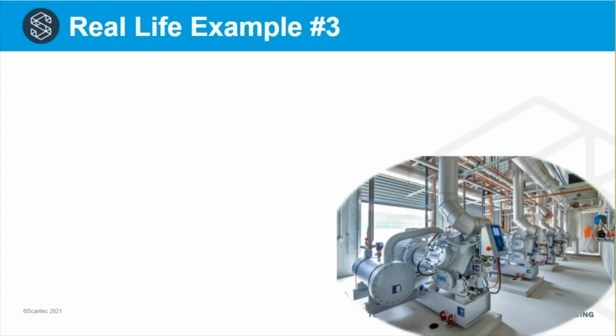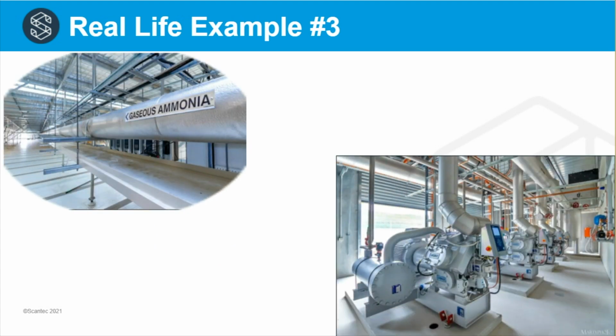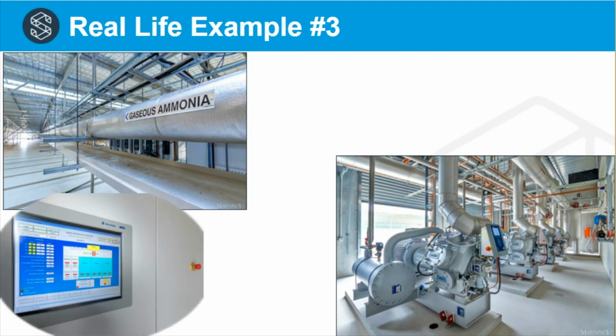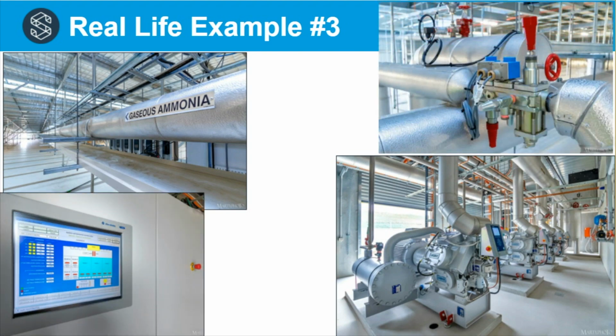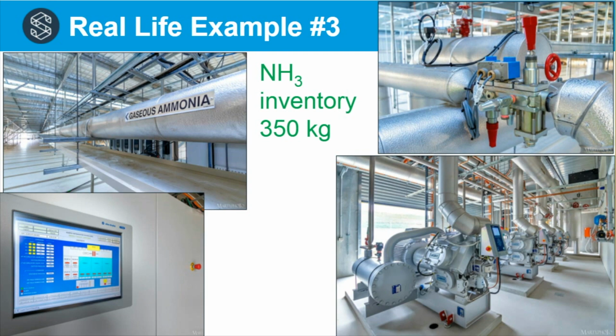Here you see some images of the new plant. The 4 compressors in the bottom right hand of the picture, the SCADA system on the bottom left hand side, and some pipe work and some valve stations, etc. Now, the ammonia inventory in this case is 350 kilos because it is all ammonia. We don't have a glycol loop for the medium temperature. It is all ammonia dry expansion. So the inventory is a little bit higher than the plant I showed you before, where we had a glycol loop for medium temperature.